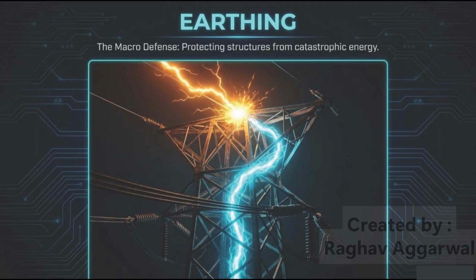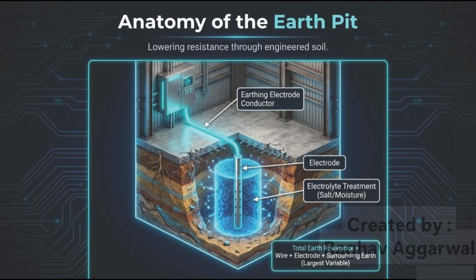They help prevent equipment enclosures and structures from reaching hazardous voltage levels during abnormal conditions. From a reliability perspective, effective earthing reduces damage that could result in costly downtime, repairs, or loss of production. Earthing protects people, structures, and equipment by safely dissipating fault energy into the earth. Let us see the earth pit. This shows the main elements of an earth pit. The earthing electrode conductor connects the electrical system to an electrode that is installed in the ground.